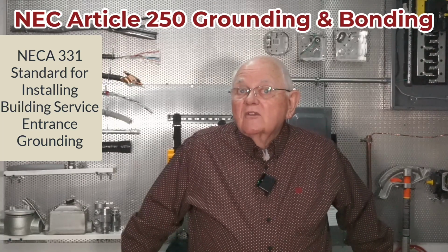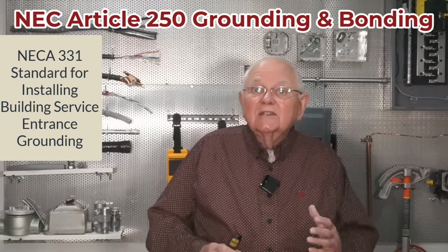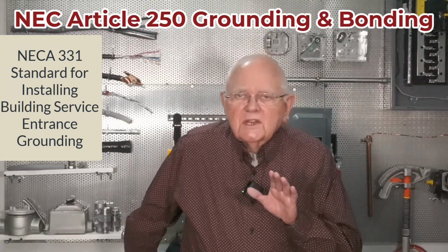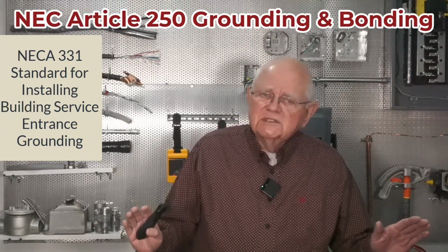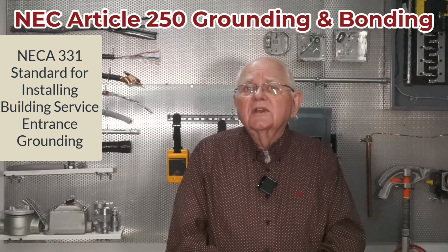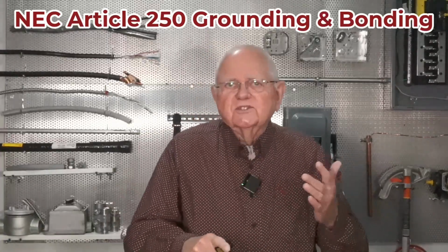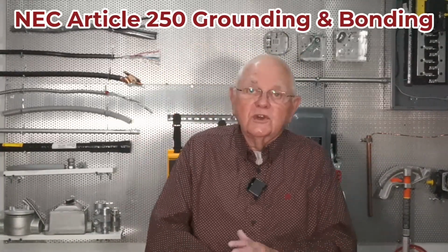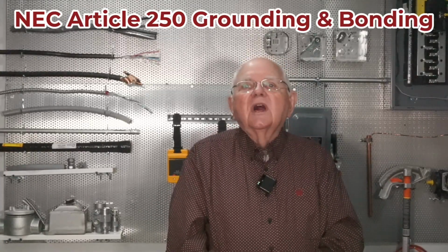As far as my ground rods, my grounding electrode system, it talks about making my actual connection to the ground rod. It should be flush or below grade. It also talks about connections for our grounding electrode system. And the ones that they list in the NECA standard are the same that we have in 250.8 for connections to grounding and bonding. You know, listed pressure connectors, terminal bars, exothermic welding, machine screws have to make at least 2 threads of engagement and so on. So anyway, you can always refer to 250.8. You're definitely going to comply with that.